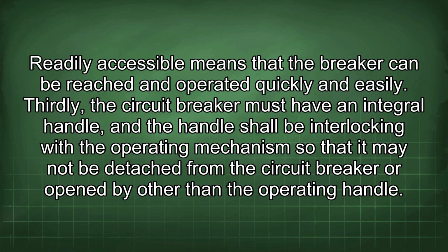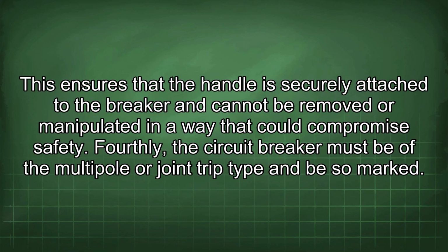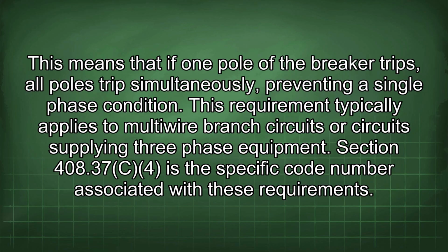Thirdly, the circuit breaker must have an integral handle, and the handle shall be interlocking with the operating mechanism so that it may not be detached from the circuit breaker or opened by other than the operating handle. This ensures that the handle is securely attached to the breaker and cannot be removed or manipulated in a way that could compromise safety. Fourthly, the circuit breaker must be of the multipole or joint trip type and be so marked. This means that if one pole of the breaker trips, all poles trip simultaneously, preventing a single-phase condition. This requirement typically applies to multi-wire branch circuits or circuits supplying three-phase equipment.